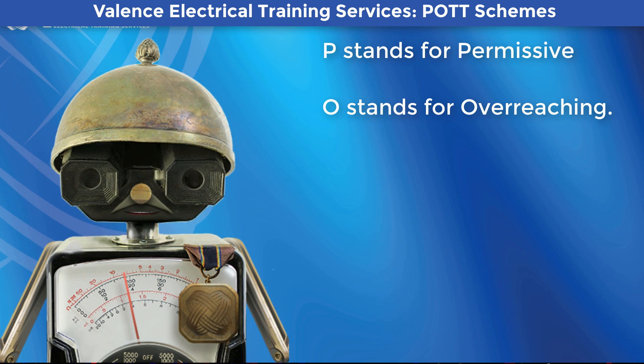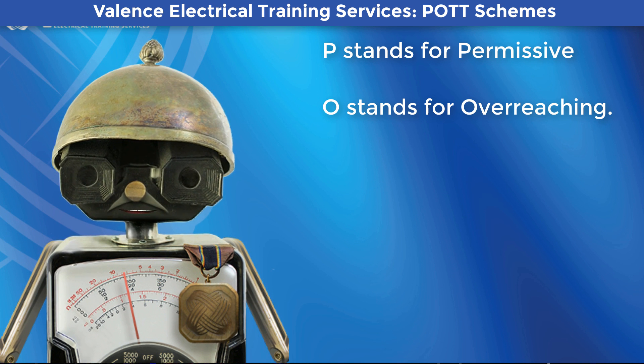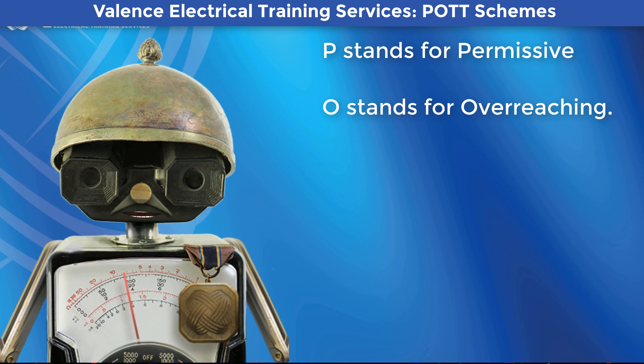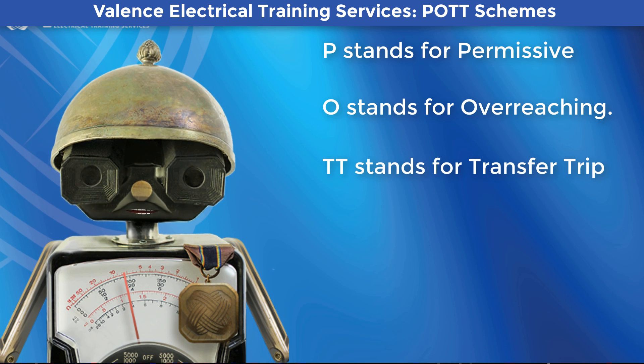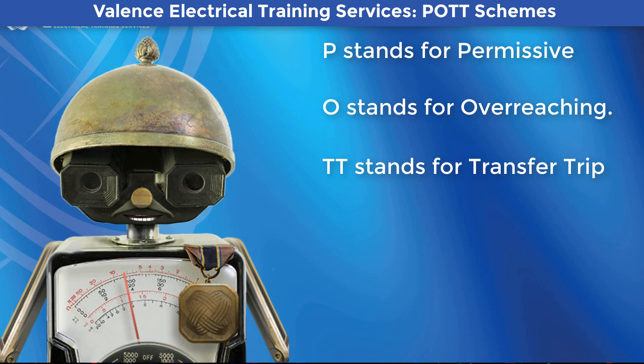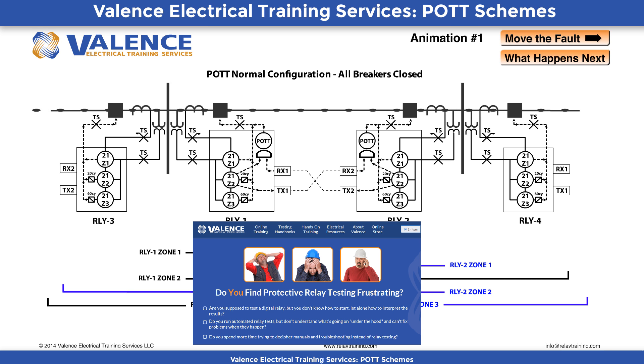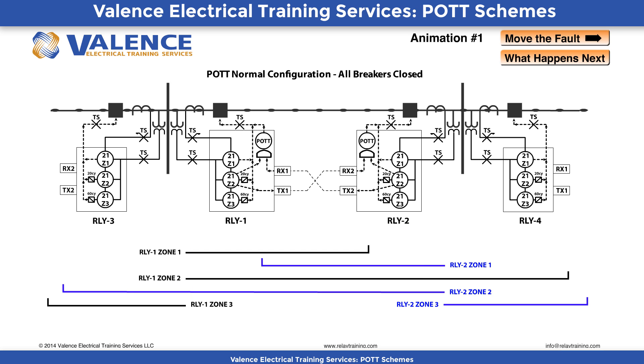The O stands for overreaching. Zone 2's pickup impedance is typically set larger than the protected line, which means that one relay must measure a Zone 2 fault for this scheme to work. TT means at least one relay is sending a transfer trip signal to the other relays in the scheme. You're looking at an animation of a traditional POTT scheme that you can find on our website, RelayTraining.com. There should be a link on the screen right now that you can open in a new window if you want to follow along. The link can also be found in the description below.